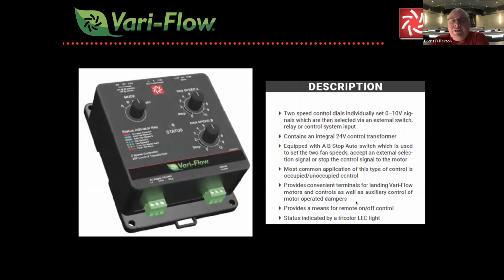In the old days, you had the option of simply a 2-speed motor, which would be a 50% split on the speed, so a high speed or half the speed, or you could have a 1/3, 2/3 split. So it would split the fan speed, and you would have to have either a switch or another type of control. That was the old days. That was back in the days when I still had hair.